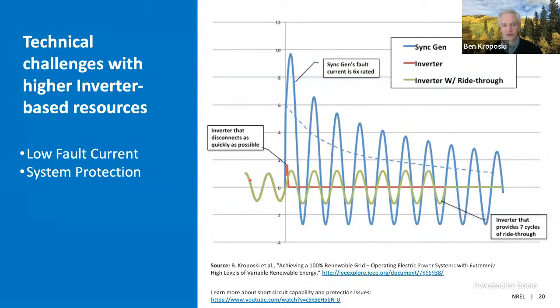When you do the same kind of fault for an inverter-based system, you actually get some different characteristics. And so in that case, you could get things where the inverter would recognize that fault is happening and disconnect very quickly, like you see in this red line, or it could ride through that fault condition for a number of cycles and then disconnect itself. But the point here is that either of these or neither of those look like the response characteristics of a synchronous generator. And so therefore, we need to come up with new ways of identifying that faults are happening on the grid when we have these high levels of inverter-based systems. And the coordination of all the protection devices needs to be understood and properly developed to handle these type of fault conditions with high levels of inverters on the system.